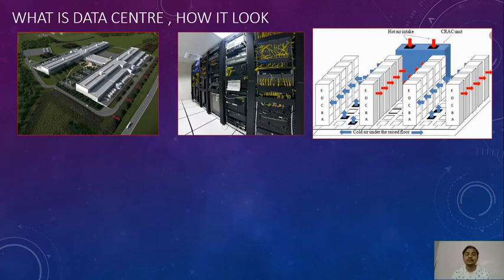So there are two types of data center models. One is the raised floor, where your entire data center is on a floor raised above the actual floor, and they pass the cool air inside the racks and take the hot air out through this raised floor. So when you pass through this corridor, this aisle, whatever you call it, it's okay, you don't feel it warm. But there are some old data centers that don't have this raised floor. So what happens when you cool your compute unit is that the hot air comes to this passage.